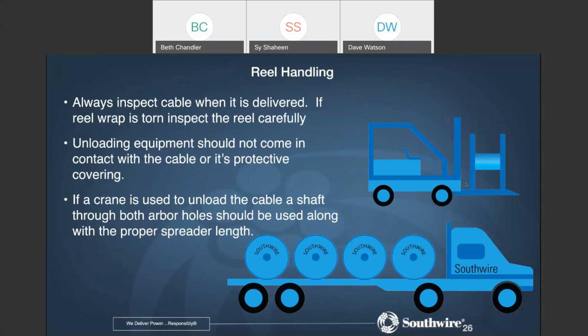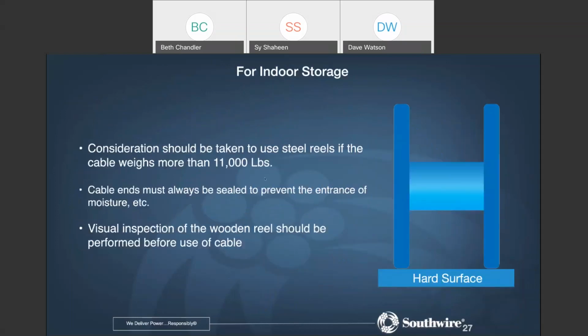Again, through my experience at the data centers, and for that matter any job site, this is really how you want to unload it. And if you have these really heavy reels that are coming on a flatbed and you want to pick them up with a fork or a crane, make sure you get the correct spreader width so you can unload them off the truck. We really recommend that consideration be given to steel reels if the cable weighs more than 1,000 pounds. So if the reel with the cable weighs more than 1,000 pounds, you really want to look at steel reels. Always have the reels on a hard surface.